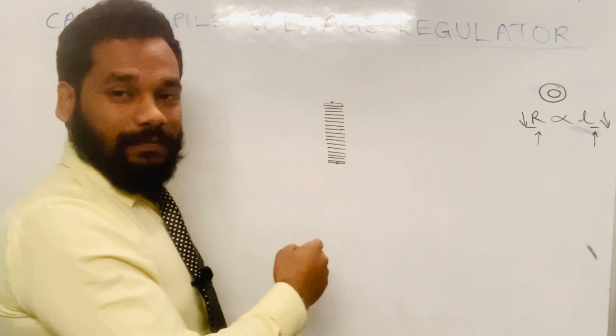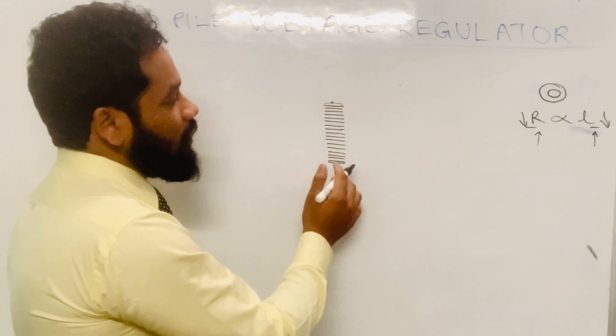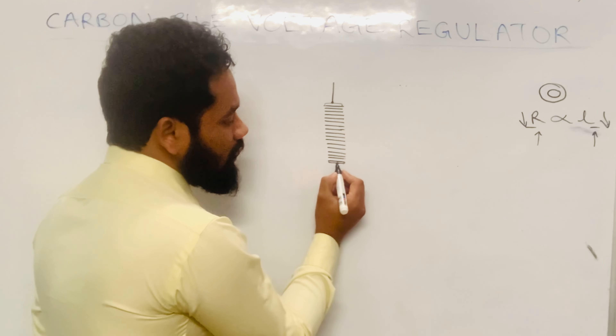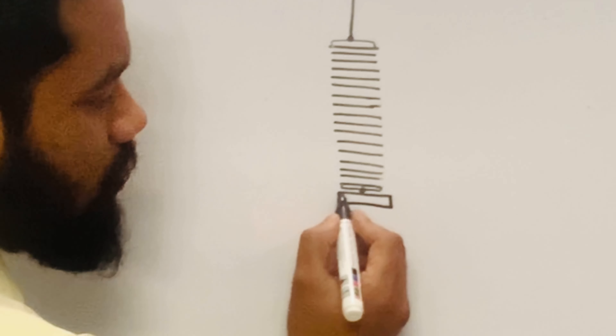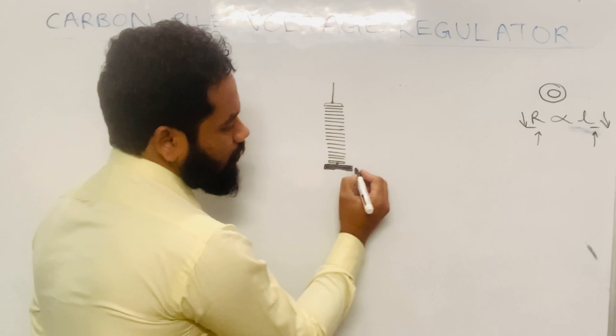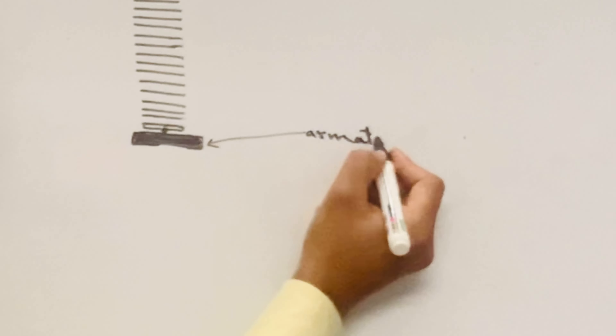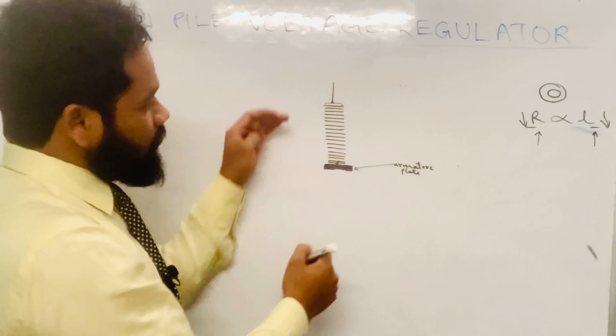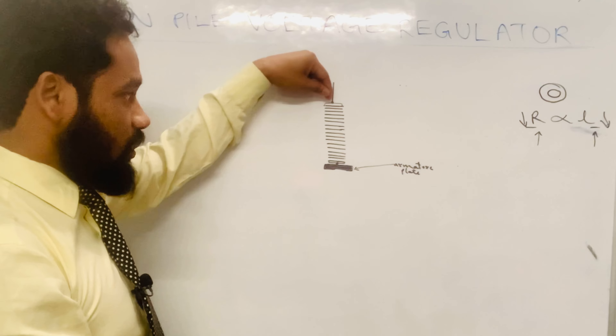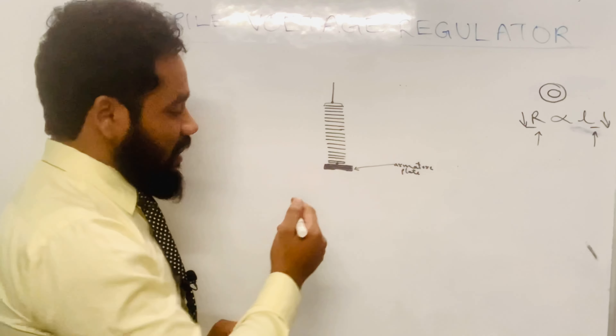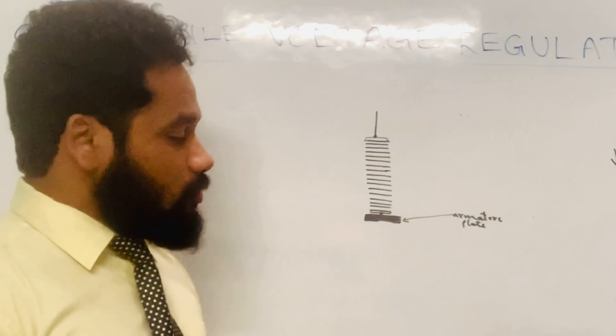In addition to this carbon pile, it should have contacts for use in a circuit. One contact is taken from the silver contact, and the other contact is connected to a plate called the armature plate. When the regulator is designed, this armature plate is pushed to compress the carbon pile. From one end of the carbon pile there is a compression screw, and from the other end is the armature plate. The armature plate is pushed by a compression spring or control spring.